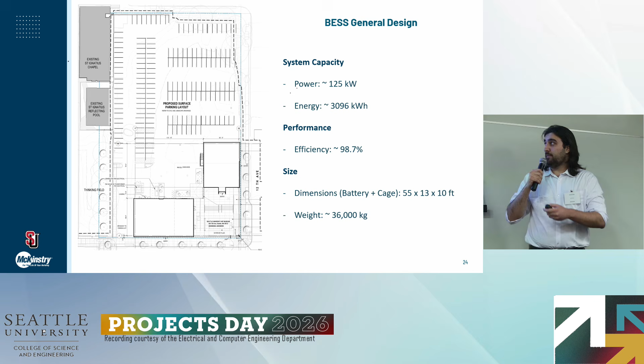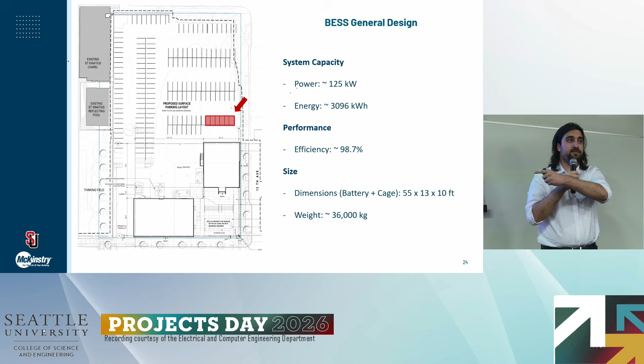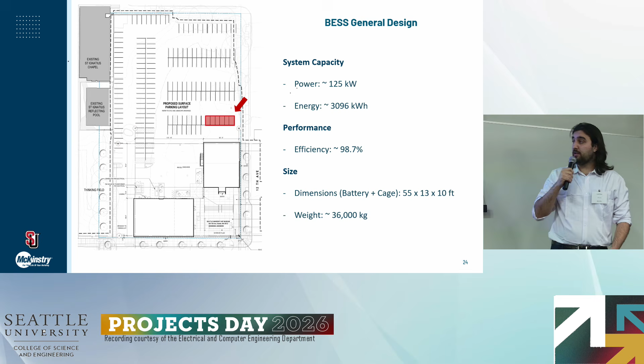The final system design provides 125 kilowatts of power and a total energy capacity of approximately 3,000 kilowatt hours. The image on the left shows the map of the museum's parking lot based on the battery's dimensions and safety cage. Approximately 6 parking spaces are allocated for the battery system while applying the required safety clearance and code considerations for battery energy storage systems.